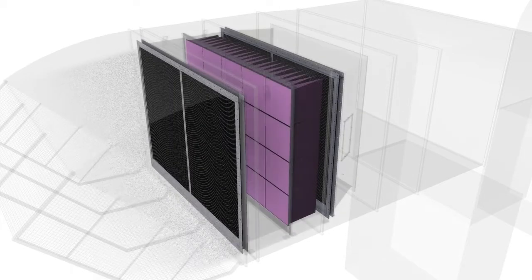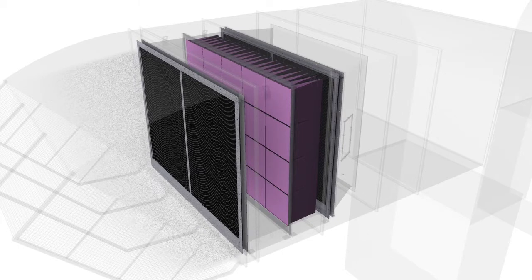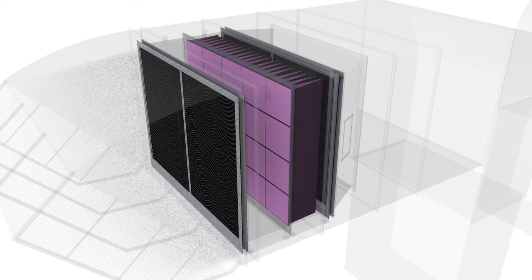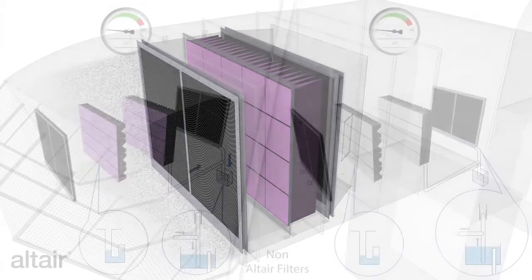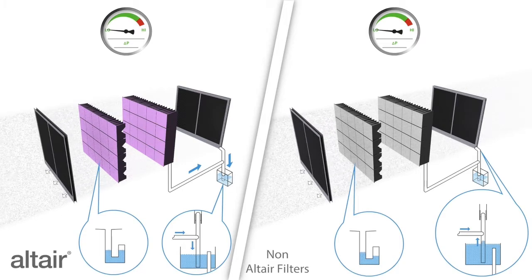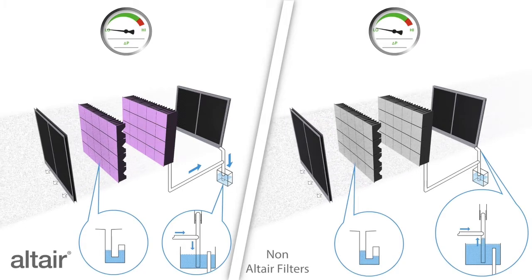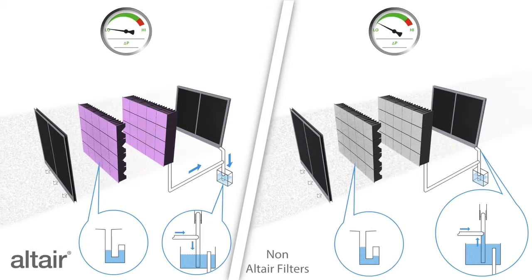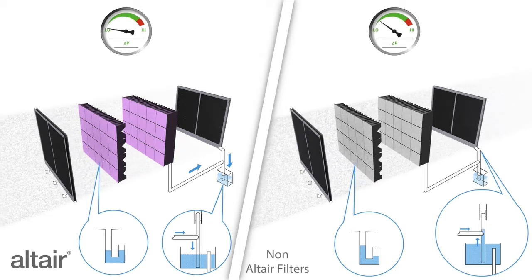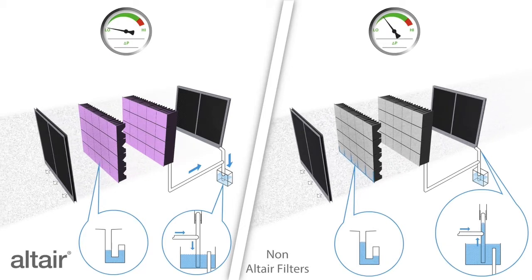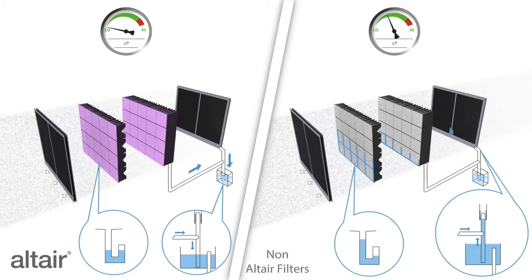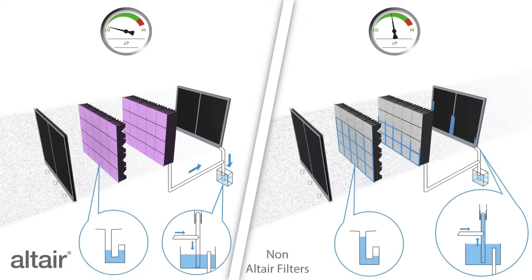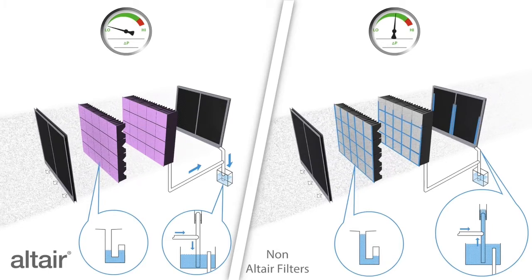Understanding the interaction of the four stages of filtration and the critical drainage system is fundamental to the operation of the Altair System 2 and Aquila. Third-party filters may not meet the demands placed upon them and may allow significant levels of salt and moisture to bypass the system, causing the GT to ingest significant amounts of salt. For example, hydrophobic filters used in many applications do not necessarily add value in Altair System 2 or Aquila since the drain system design may become overwhelmed, causing saltwater ingestion.